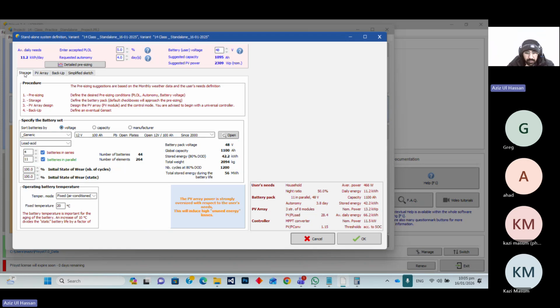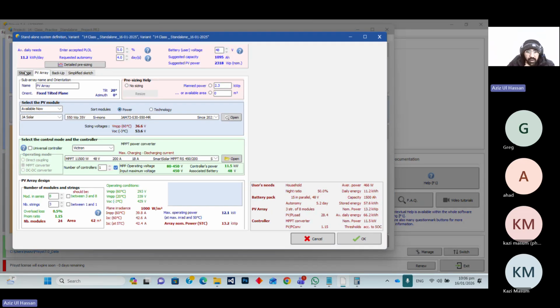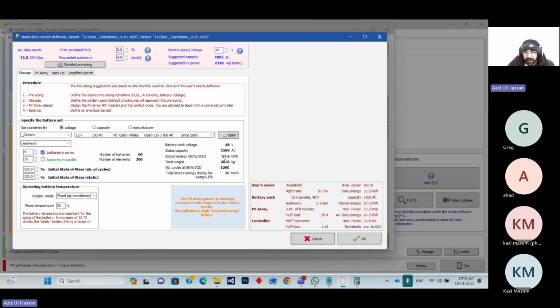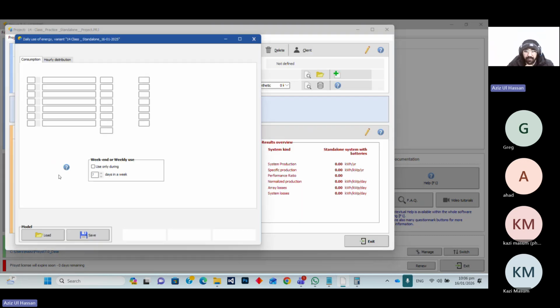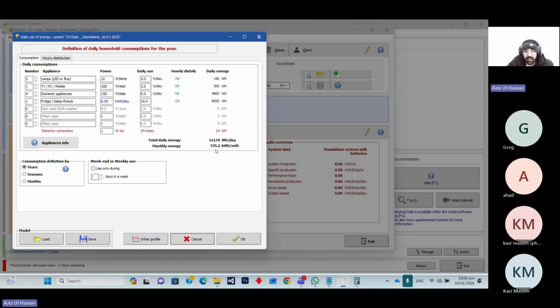We have just selected the storage. And then we have selected, if we use 12, 13, 14, 15, like we can use this storage system. We have 57.6 kilowatt hours of storage in our system. And our usage is that we need 335 kilowatt hour per month. Daily usage is 11.174 kilowatt hour. So you need 11 kilowatt hour per day.